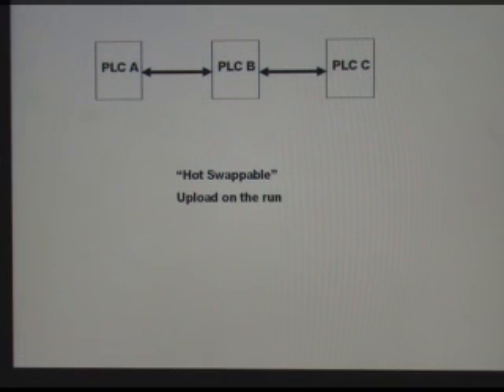The other thing is, obviously, you can't have different programs in these 3 PLCs, so you have to be able to upload new programs on the run. You have to take this offline, upload it, and then bring it online. It'll raise an error, but then you upload this one, and then these two will start to agree. Then you upload this one, and you end up again with all 3 of them being able to agree on how to control the equipment.